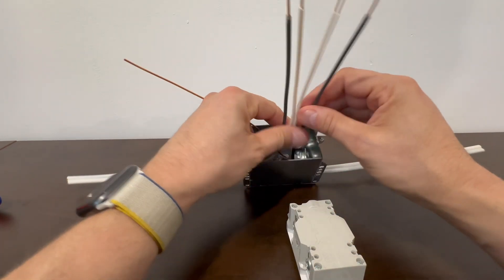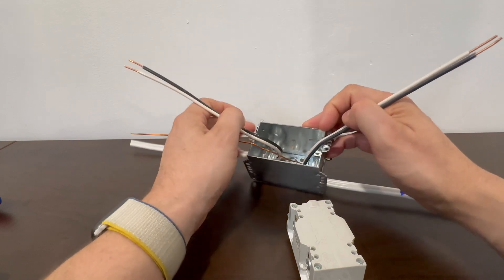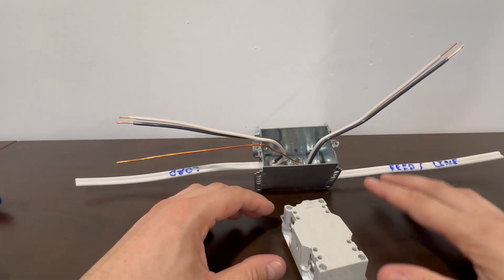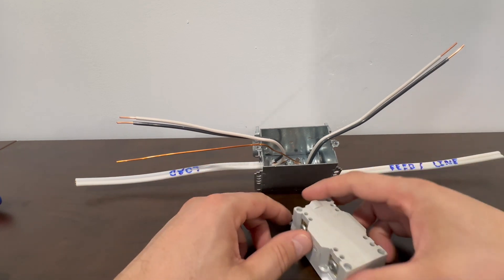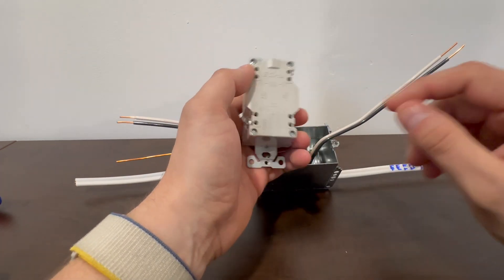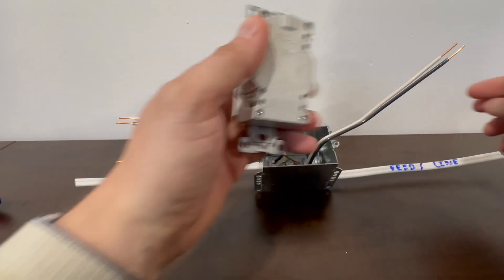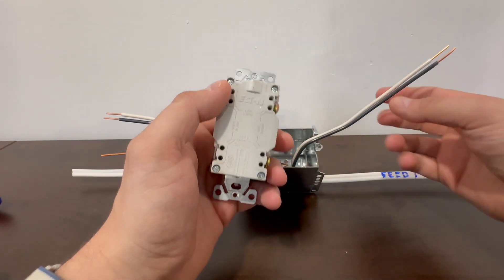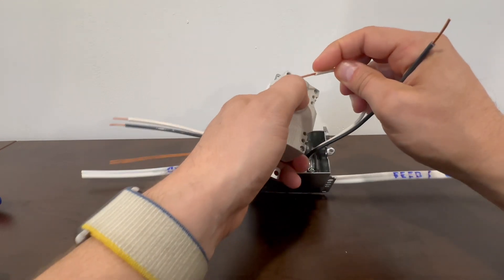So what we're going to do is we're going to separate our line side from our load side, make sure they're completely separated so you don't get them mixed up. The GFI, if you do get them mixed up, the GFCI will not work. What I tend to do is hook up my line side first. So right up here I see I have my line side and this is my line side. That would be coming from my breaker panel or power source.